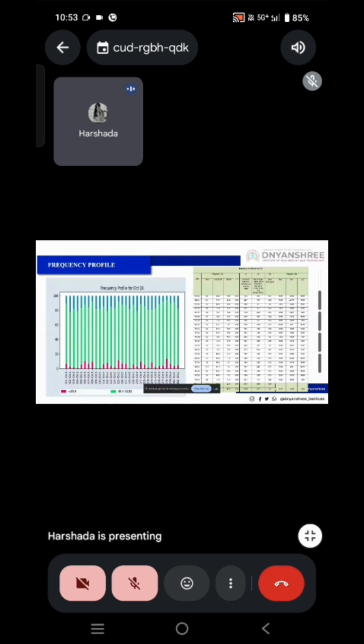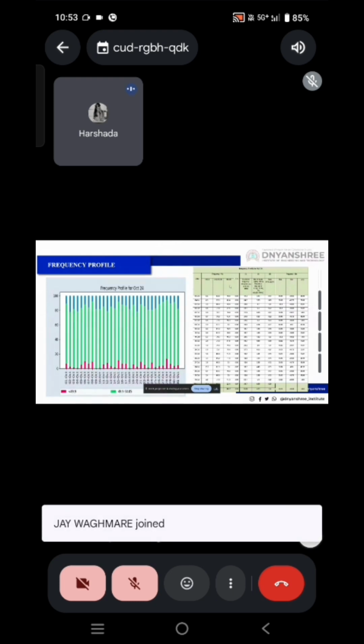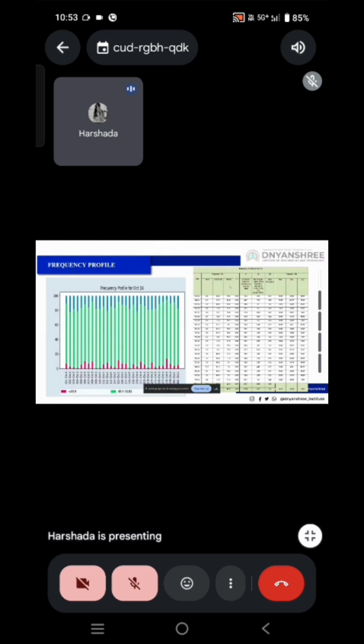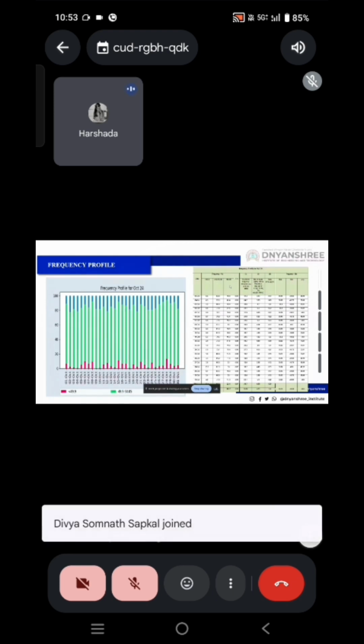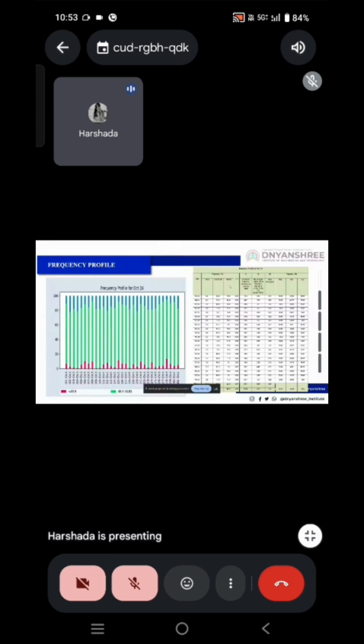This waveform shows that when the line goes down, it means load is more than generation, causing a frequency drop. When the line goes up, it means generation is higher, so frequency increases. According to IEGC, the safe frequency range is between 49.90 hertz and 50 hertz.